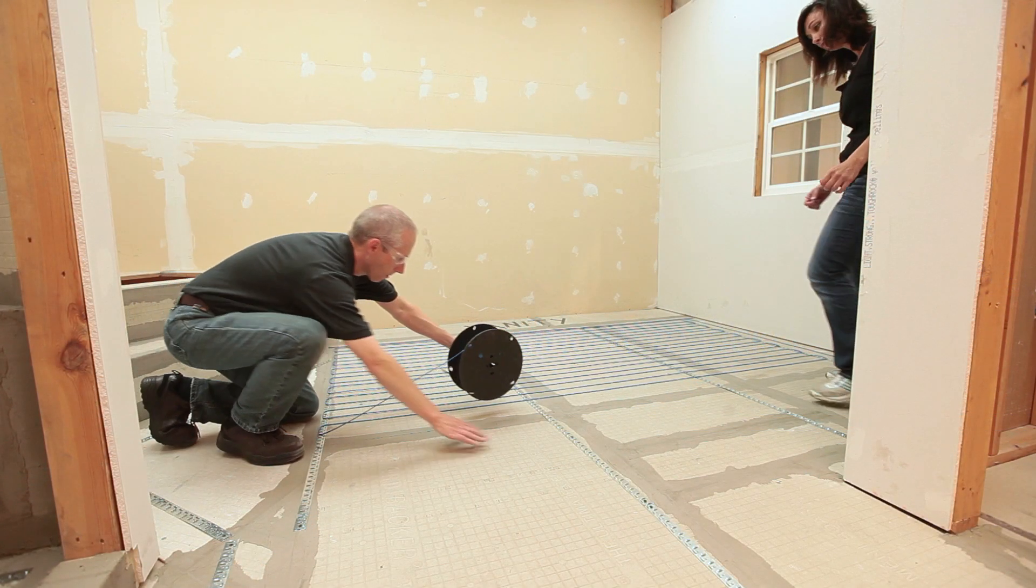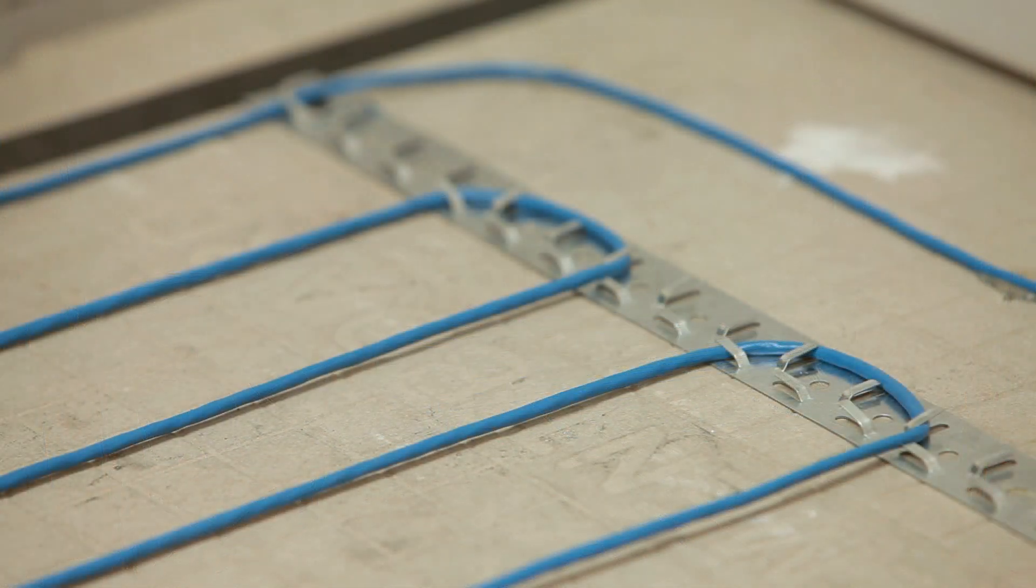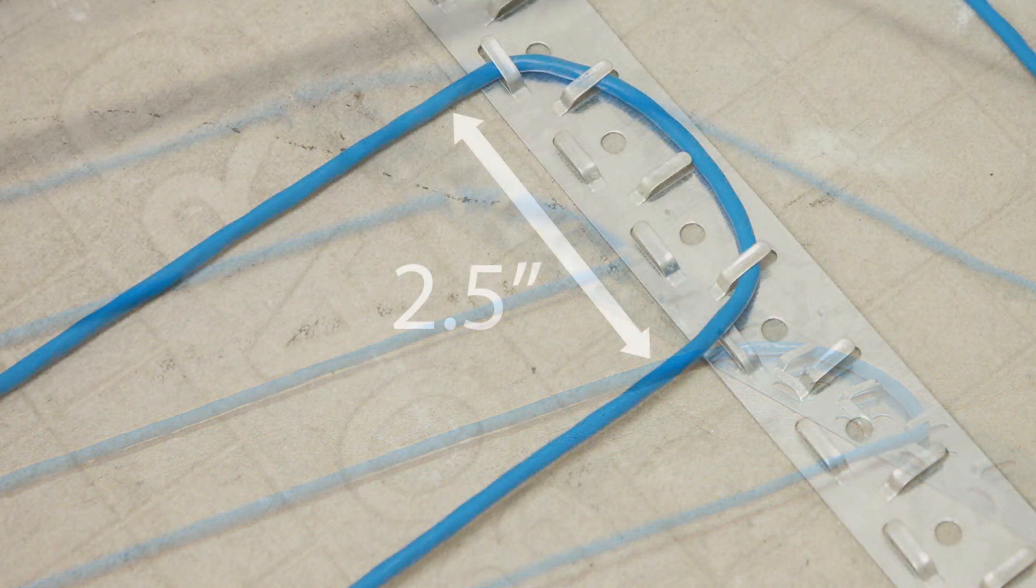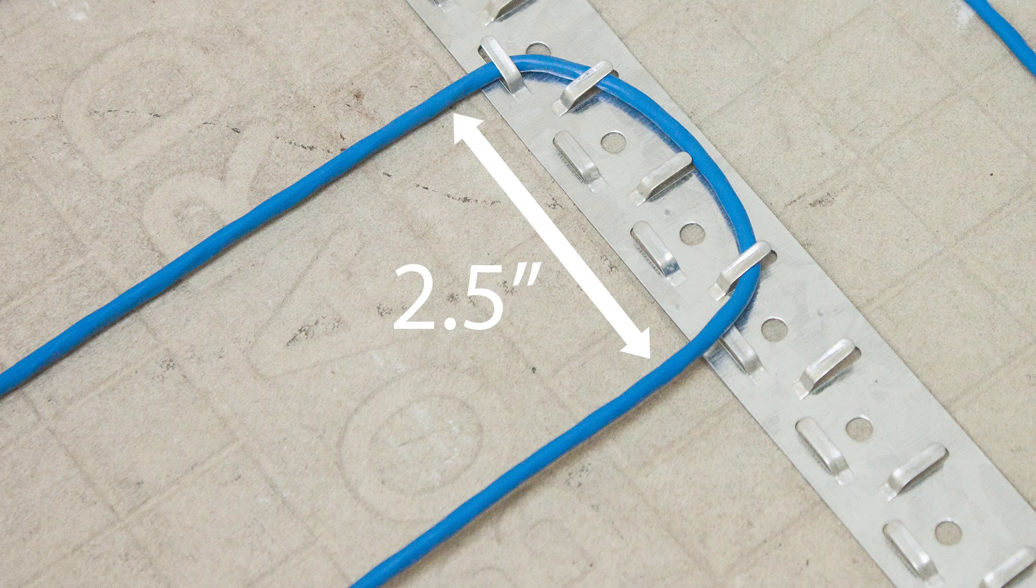Feed the heating wire between one row of strapping and the other, keeping in mind your desired spacing. Each vertical tab is a visual indicator of one inch spacing. For two and a half inch spacing, wrap the wire around three vertical tabs, plus one horizontal tab.